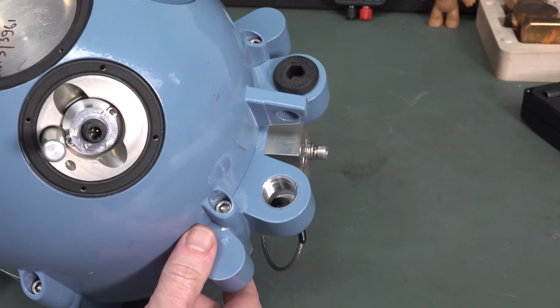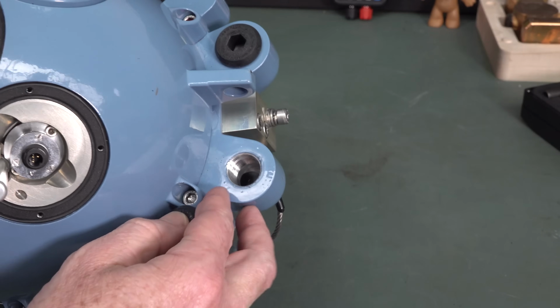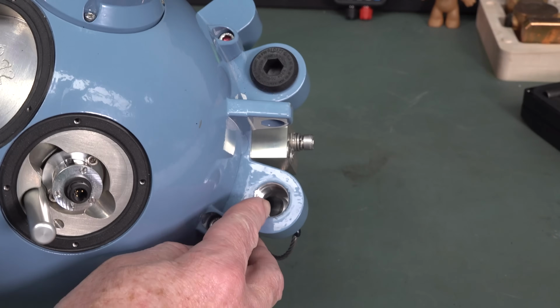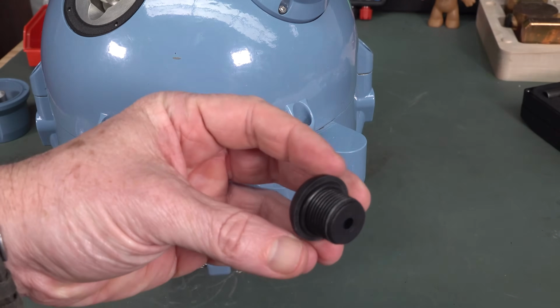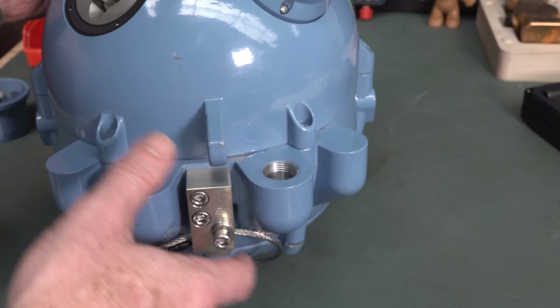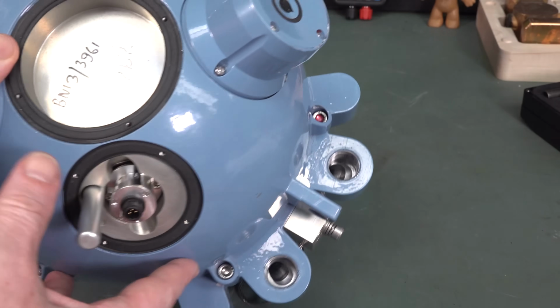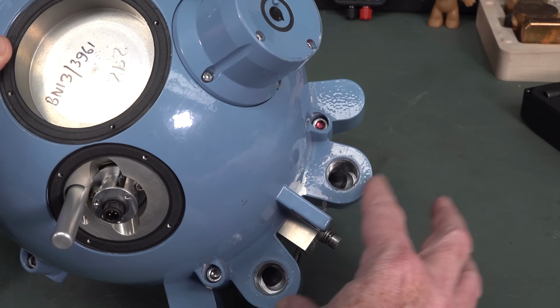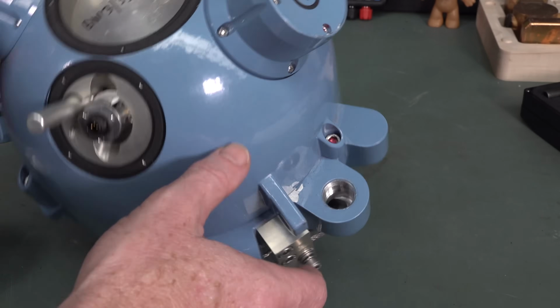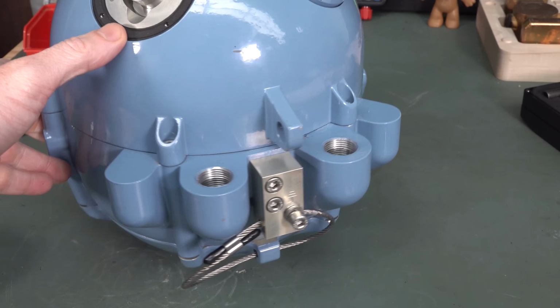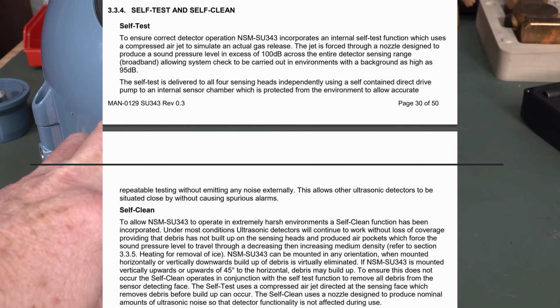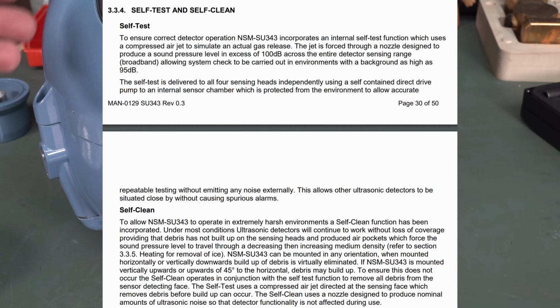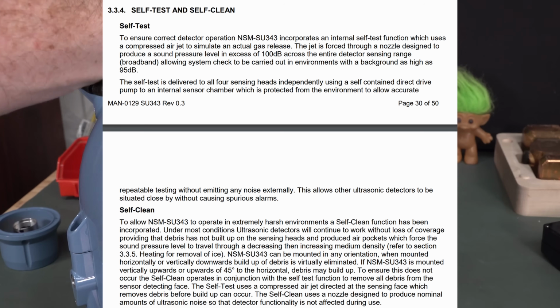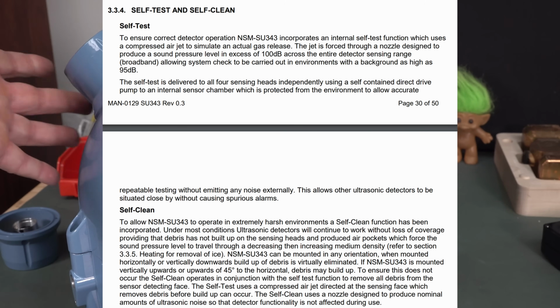It almost looks like inside this there's a port going in there. And sure enough, that's got an O-ring on it. That may be part of a pressure self-cleaning system, so you may have to hook up, as a guess, a pressurized gas system, ironically, to actually apply pressure to the sensors to test them.